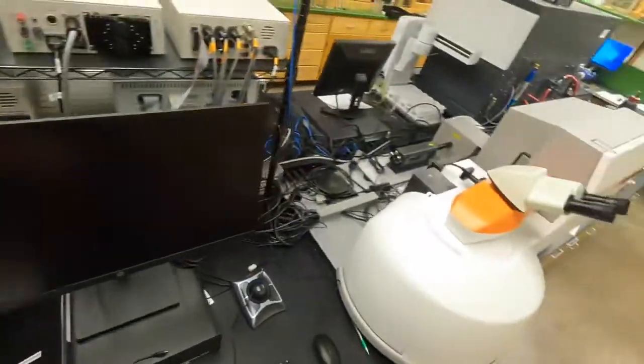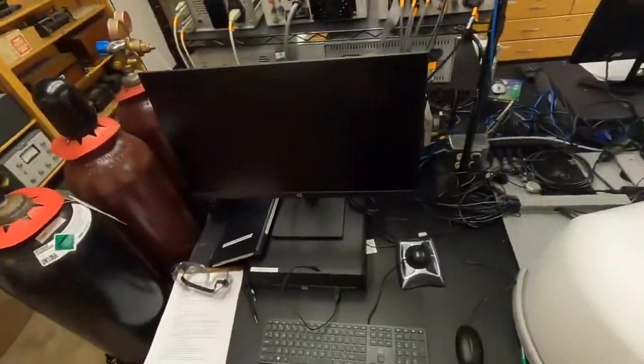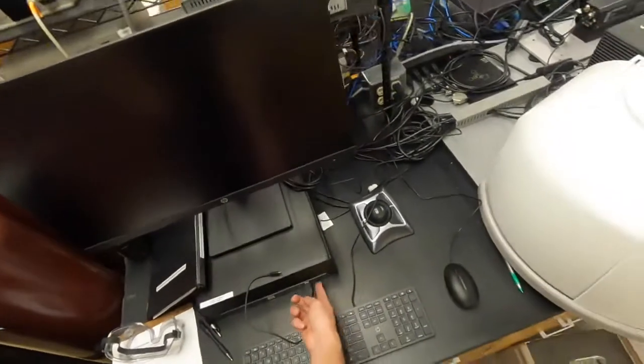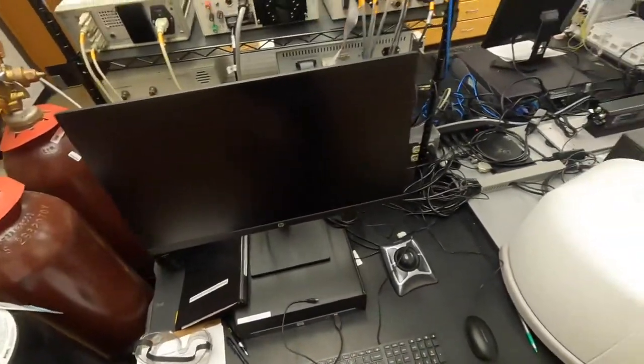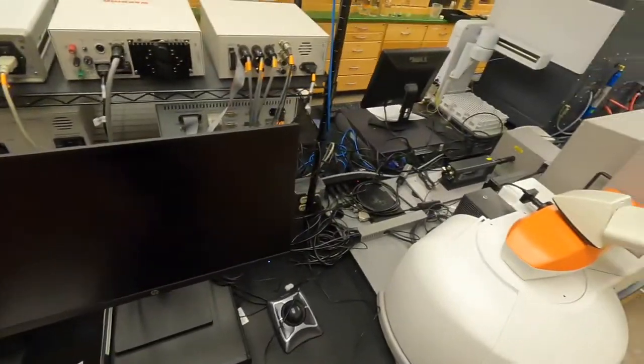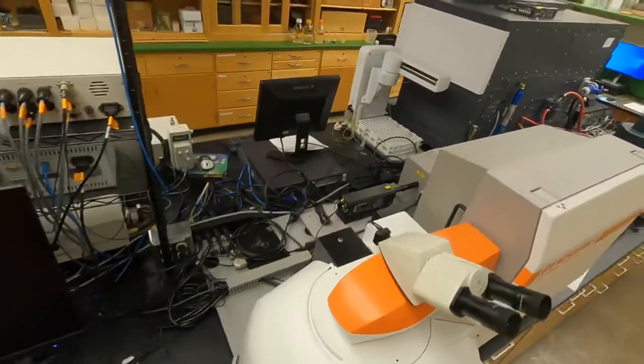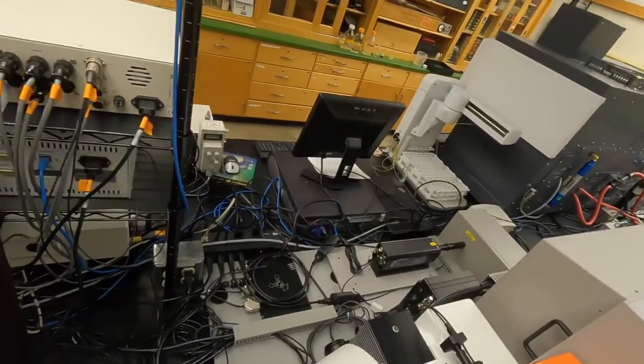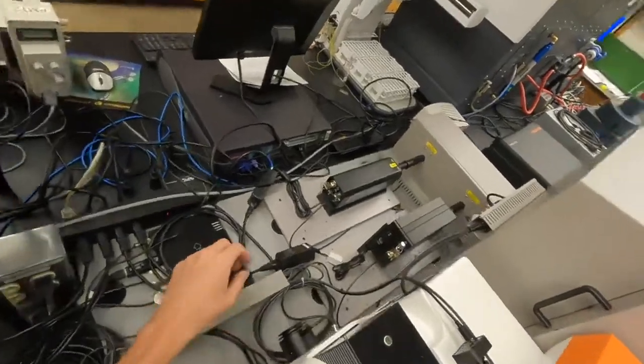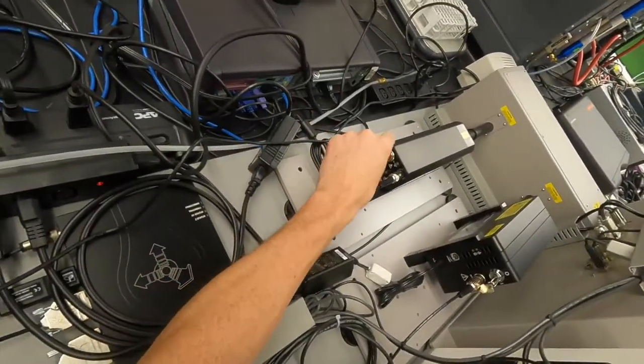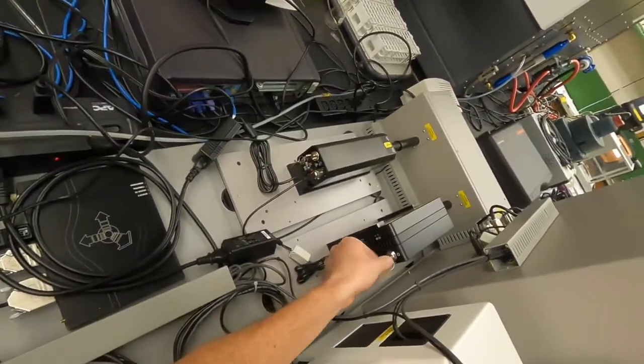Okay, so I'm gonna show you guys how to start up the Raman microscope. You first start off by just powering on the computer, because usually the computer's fully shut down. And then the next step is to turn on these lasers. Usually you want to try to turn them on like 20 minutes beforehand, because they take a second to warm up. So for this back laser, you just turn this key upright. And then for this laser, turn this on.